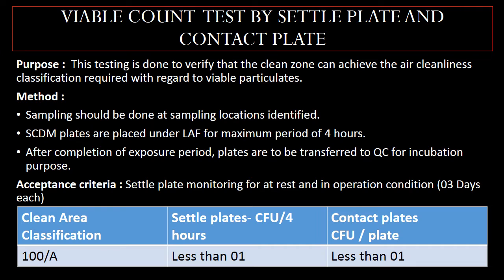The next important qualification test is the viable count test by settle plate and contact plate method. This testing is done to verify that the clean zone can achieve the air cleanliness classification required with regard to viable particulates. During execution, sampling is done at identified locations and SCDM (soybean casein digest medium) plates are placed under the laminar air flow unit for a maximum period of four hours. After the exposure period, the plates are transferred to QC for incubation. The acceptance criteria is less than one colony forming unit for exposed settle plates and contact plates to comply with Grade A or Class 100. This monitoring shall be done at rest and in-operation conditions for three consecutive days.